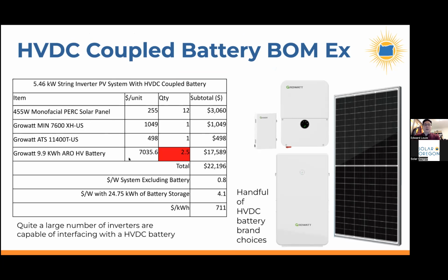And then in order to allow these systems to keep the lights on during a blackout, the system needs an automatic transfer switch to disconnect the house from the grid so that you're not backfeeding energy and potentially harming a person trying to restore power on the grid. In this case, this company makes a transfer switch that's less expensive, but we will go later into a slide that explains why it's less expensive and perhaps one of the cons or caveats of choosing a transfer switch that's less expensive.